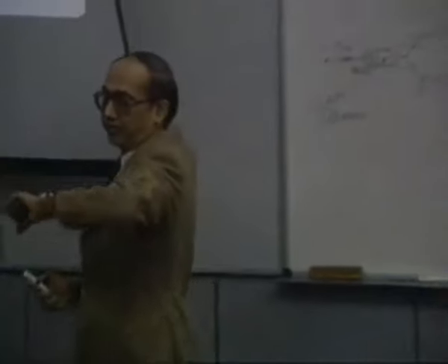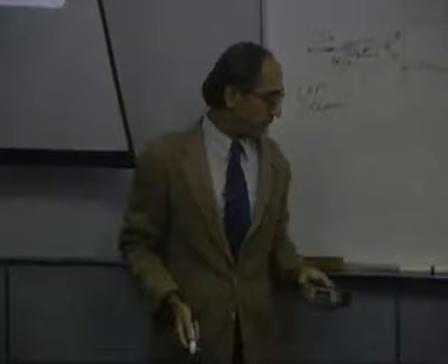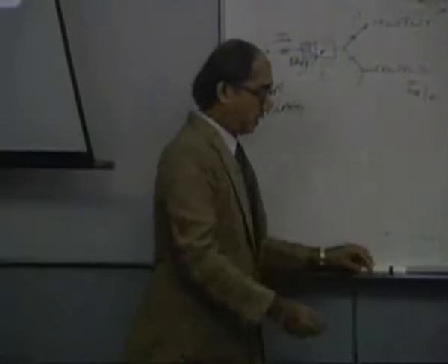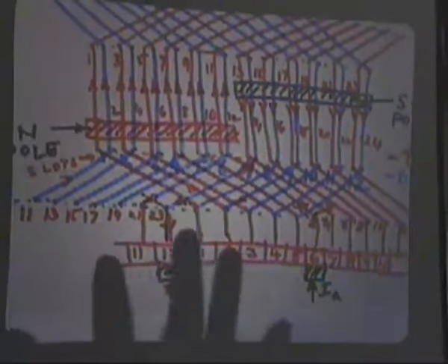Okay. So, this is a picture of a two pole arrangement. As I made it clear earlier, in a two pole machine the lap winding will be the same as the wave winding, and we can draw the armature winding like this and locate the brushes and the commutator segments. Commutator segments are connected to the ends of the coils, and by carefully traversing through the current route we will have the location of the brushes appropriately.